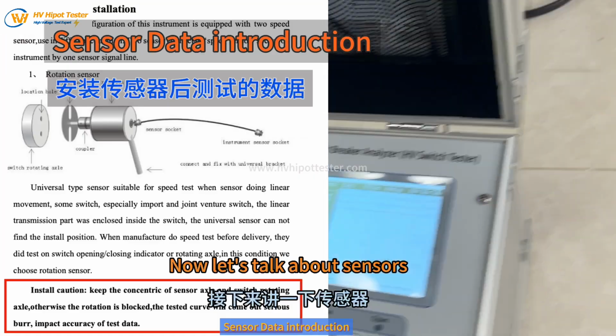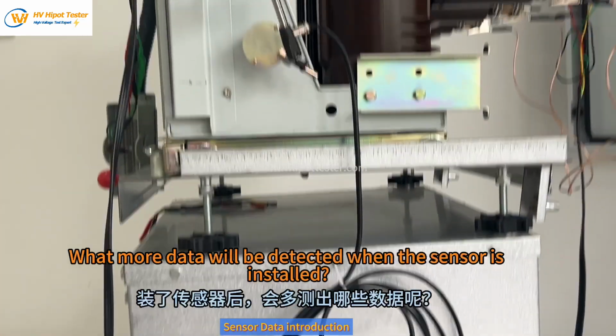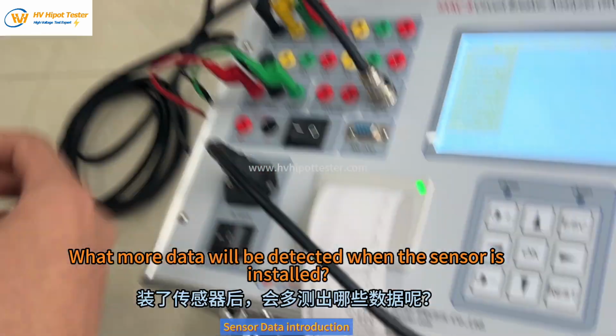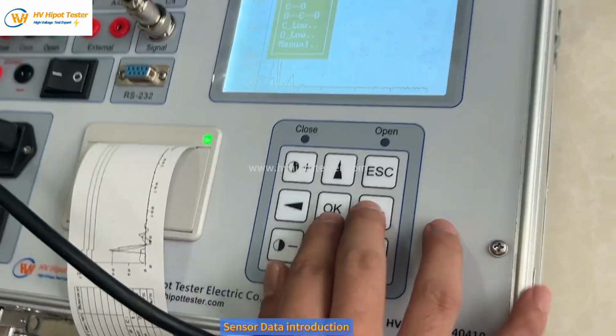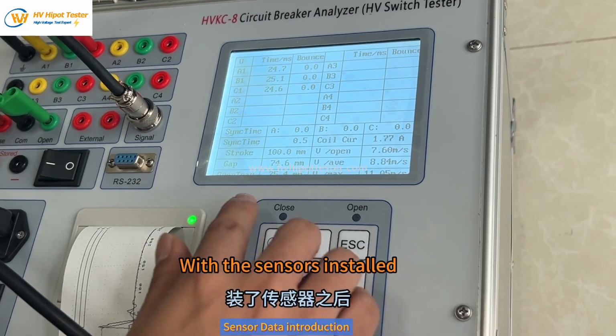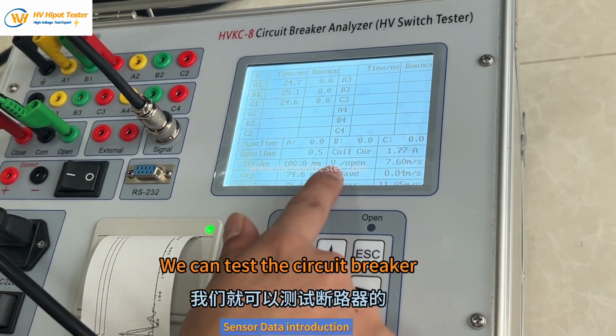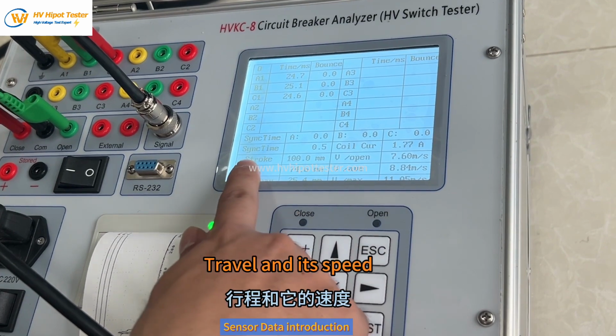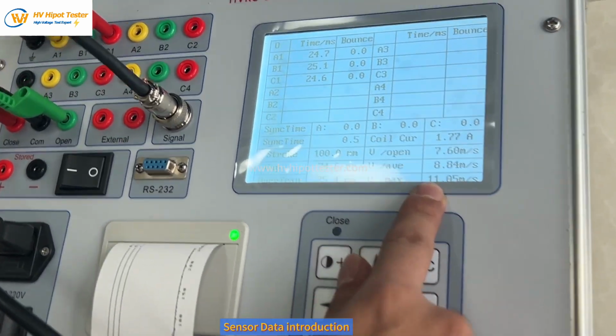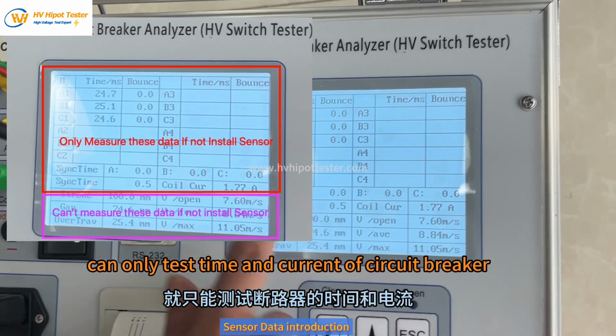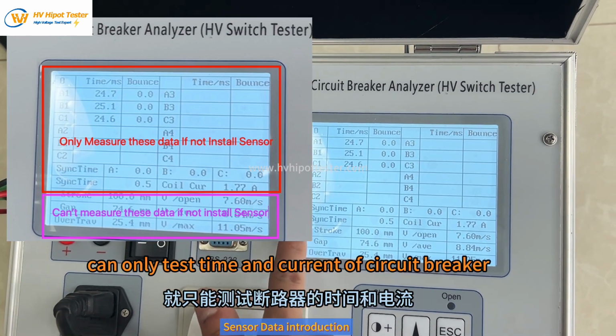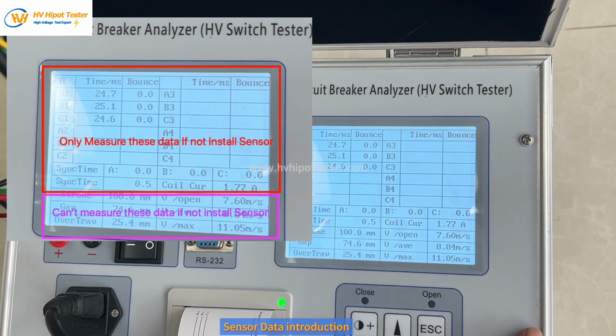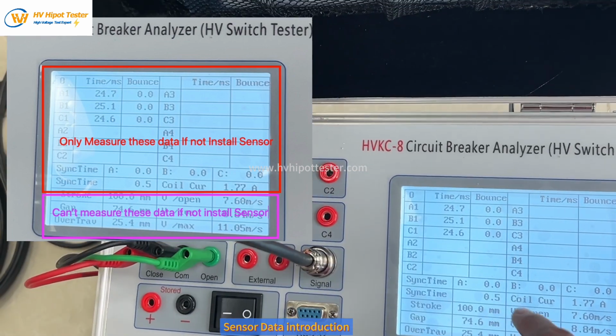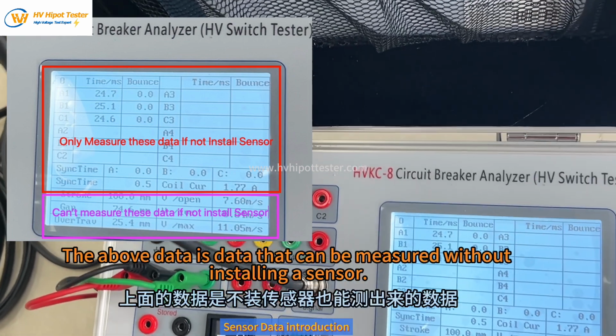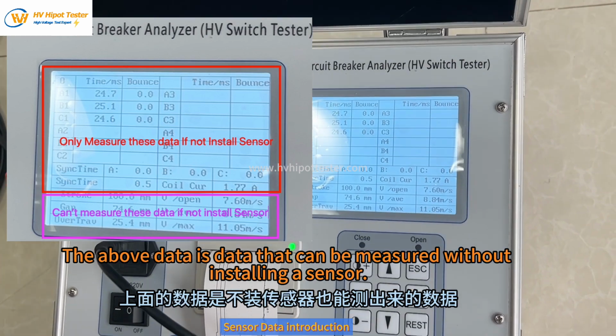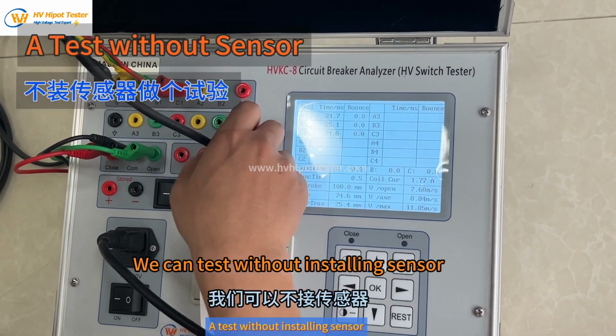Now let's talk about sensors. What more data will be detected when the sensor is installed? With the sensors installed, we can test the circuit breaker, travel and its speed. If we don't install sensor, can only test time and current of circuit breaker. With the sensor installed, can measure more data in the bottom 3 rows. The above data is data that can be measured without installing a sensor. We can test without installing sensor.